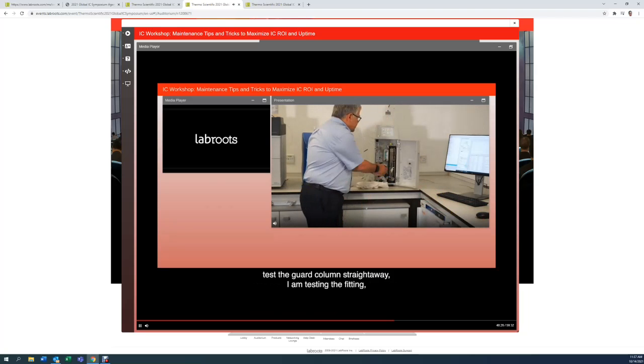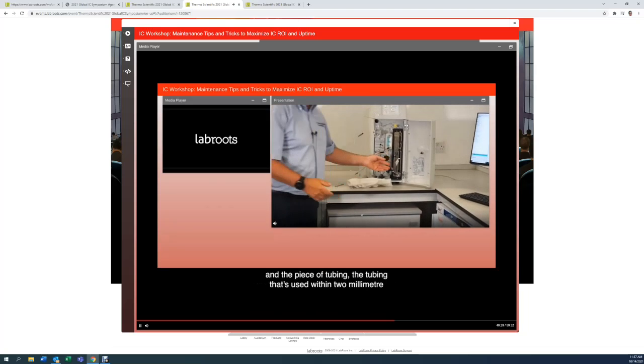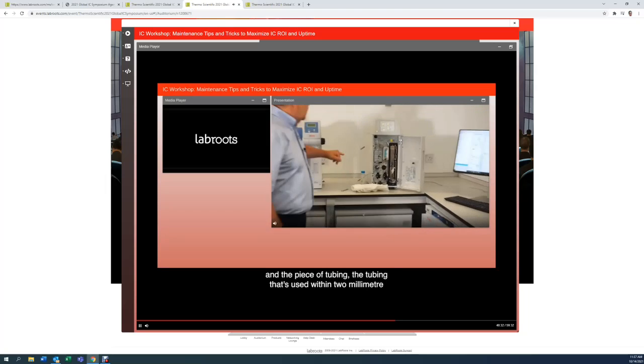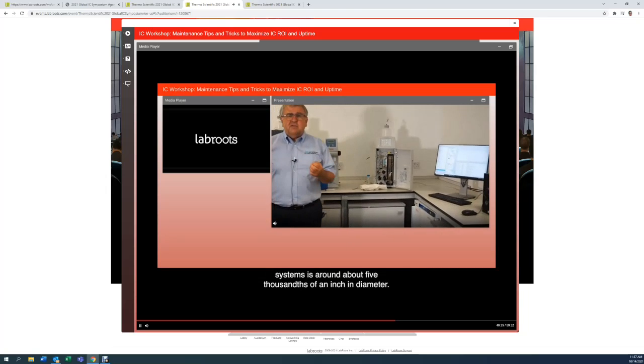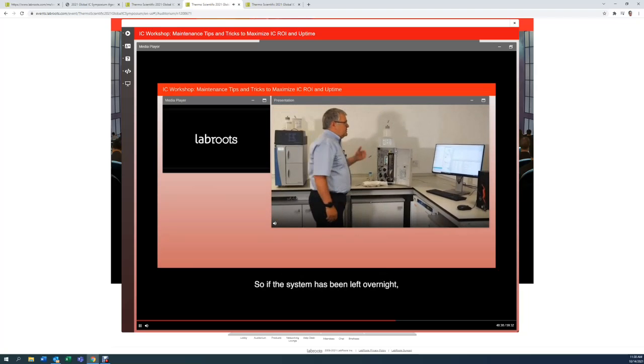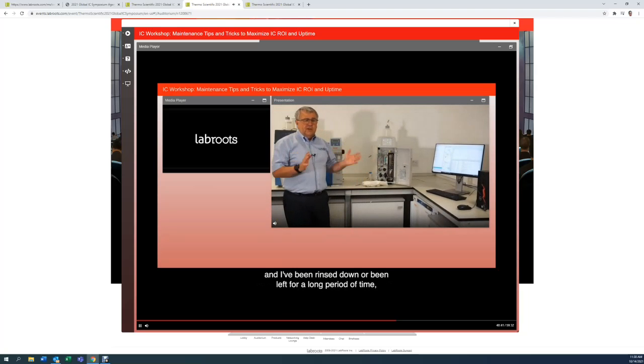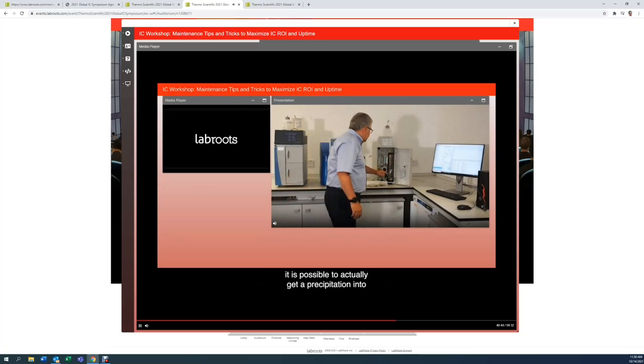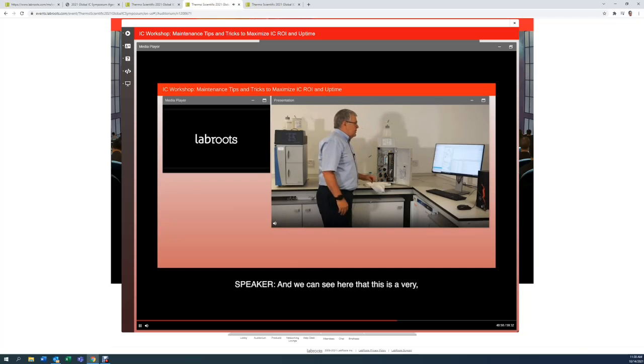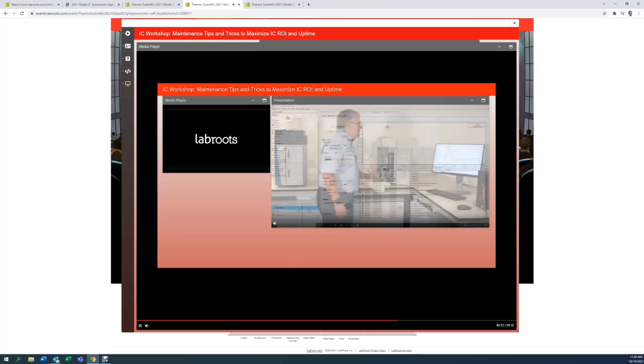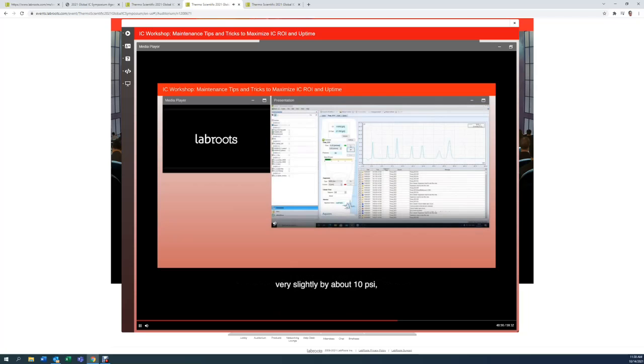You notice I'm not going to test the guard column straight away, and I'm testing the fitting and the piece of tubing. The tubing that's used within 2mm systems is around about 5/1000th of an inch internal diameter. So if the system has been left overnight, not been rinsed down or been left for a long period of time, it is possible to actually get a precipitation into the tubing, which can cause an occlusion or a blockage. And we can see here that it is a very, very narrow bore piece of tubing, and we can see that it has actually upped the pressure very, very slightly by about 10 psi, which in the grand scheme of things is not an awful lot. So we know that this fitting is absolutely fine and the tubing is absolutely fine.